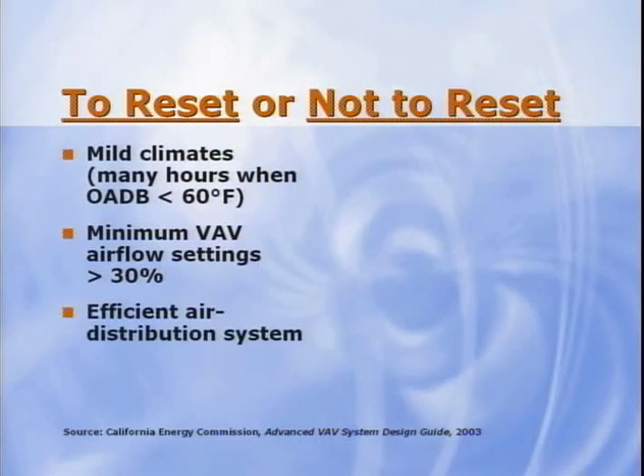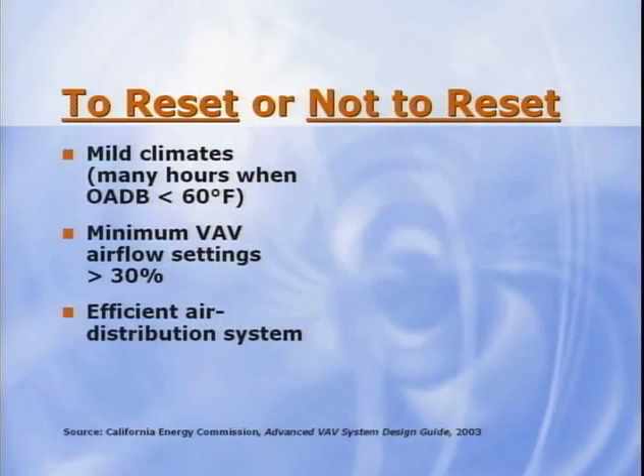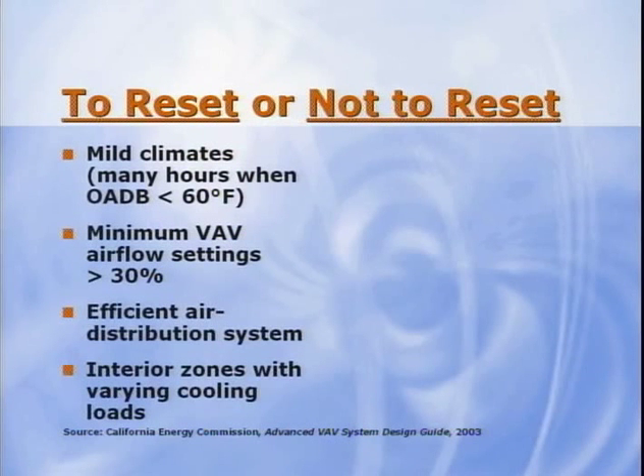Efficient air distribution system design. Low pressure losses cause less of a fan energy penalty for the higher airflows that result from raising supply air temperature. Systems with interior zones that have varying cooling loads. The variable loads may allow these zones to be satisfied with a warmer supply air temperature.